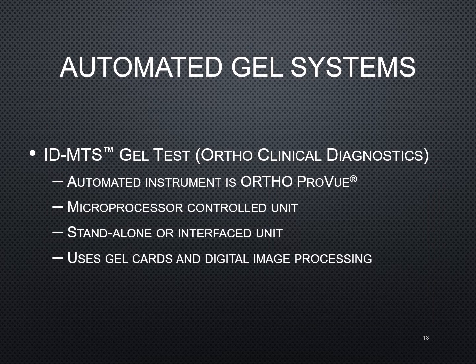There are automated systems for gel testing. Ortho originally came up with the ID-MTS gel test technology, and they developed this for their automated instrument called the Ortho ProVue. What I like to call a glorified pipetter — the beauty of this system was that you could still do the gel testing even if the analyzer was down. A lot of people do gel testing as a semi-automated system where you manually pipette reagents into the gel card and put them in the incubator and centrifuge. But the ProVue actually does everything for you — the pipetting, incubating, and spinning of the cards — and it takes digital images that the computer will interpret for you, or you can look at them as well.